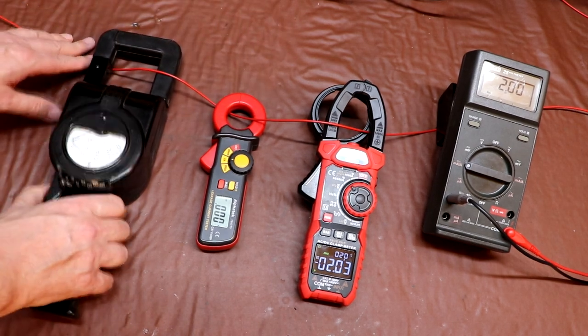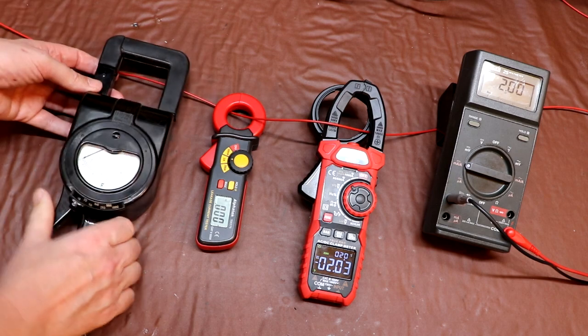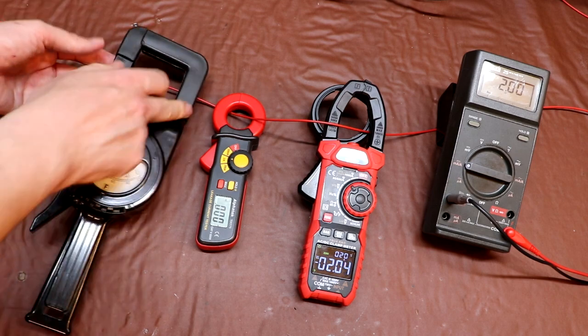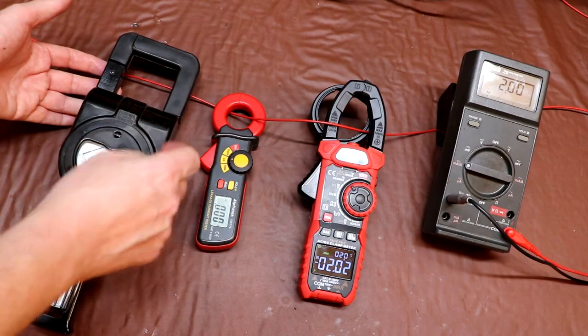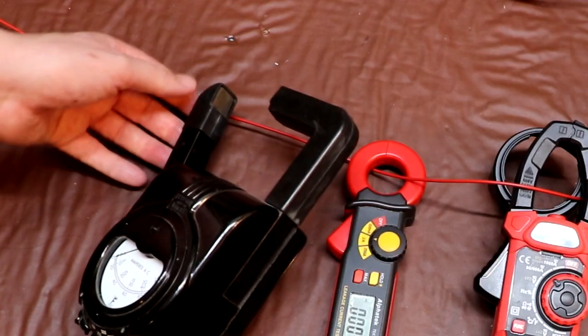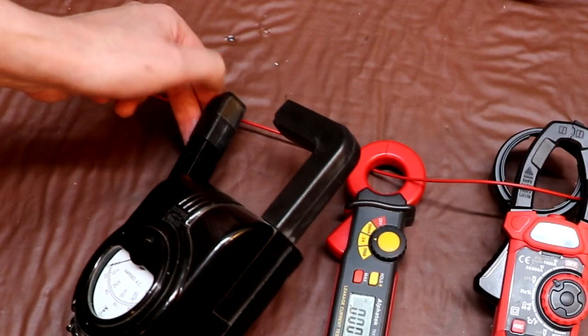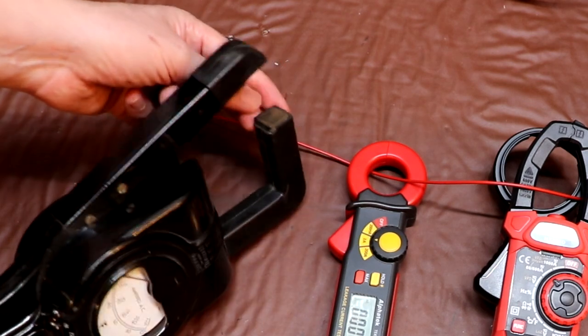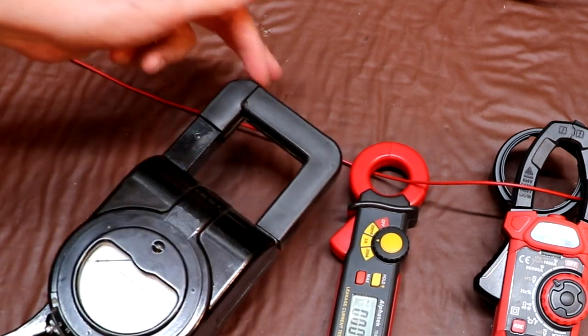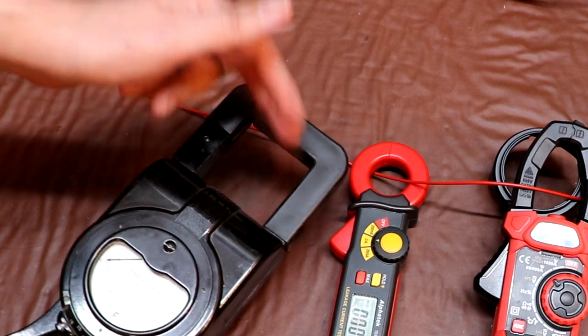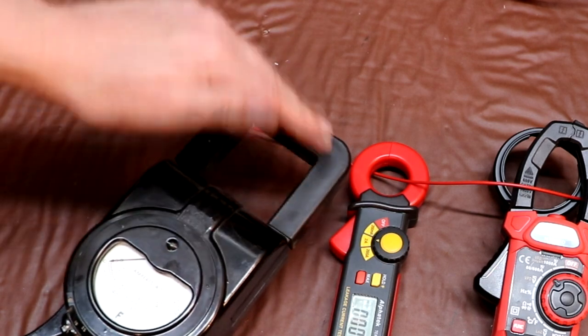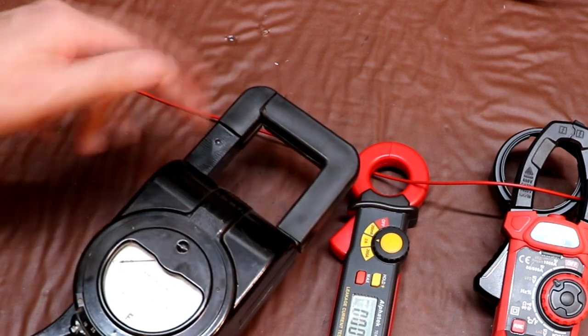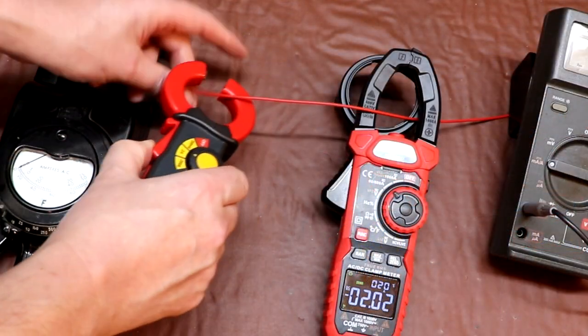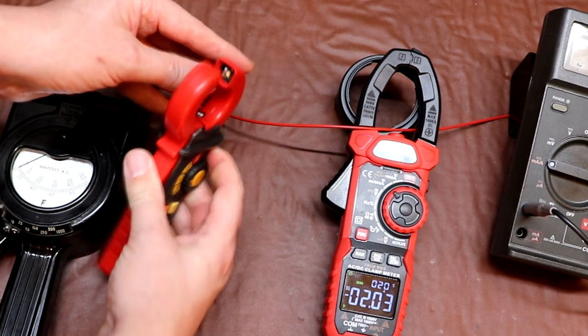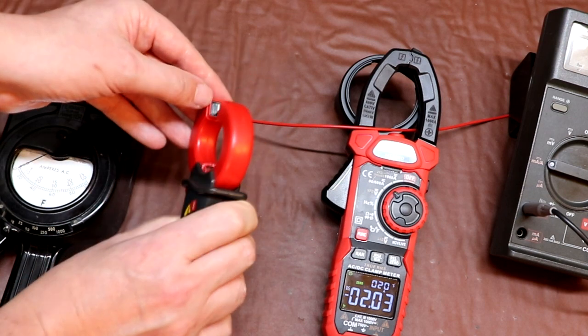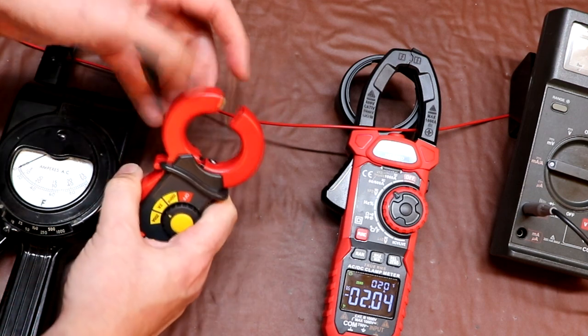Now if we just take our Ferranti meter out of circuit, you can see that we've got these tongs here, but what we've got is effectively a circular lamination. If we look at the ends of the tongs, there's a metal contact and another metal contact there, so it's metal on metal. You have to have this metal on metal contact for the magnetic flux to be able to flow easily around the circuit. It's the same for our Alphatec meter: if you look at the jaws, we've got a piece of metal and another piece of metal, and these two pieces slot together.